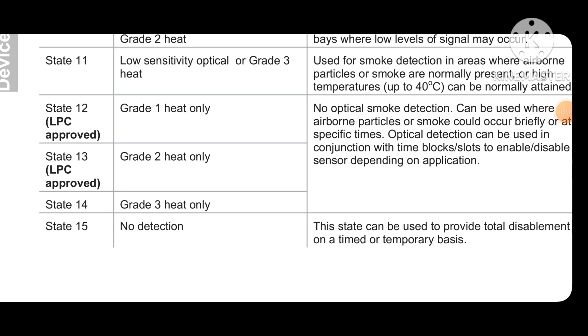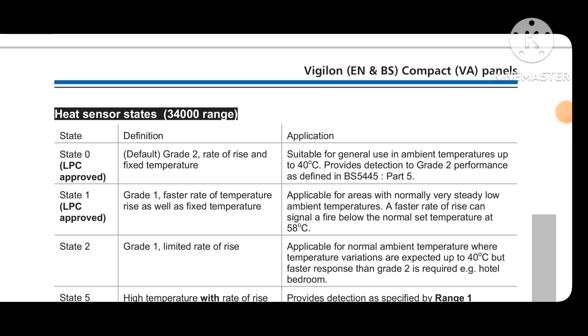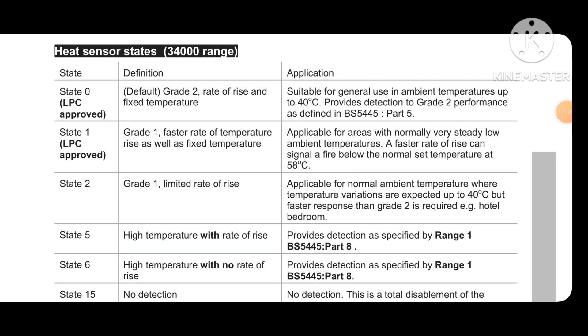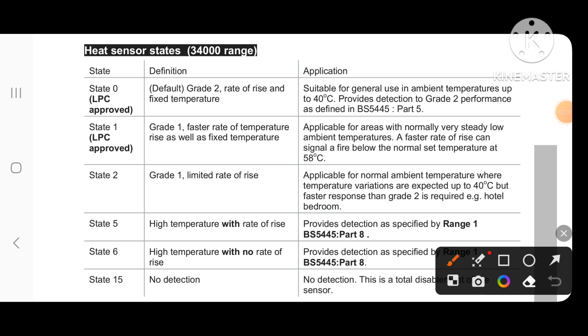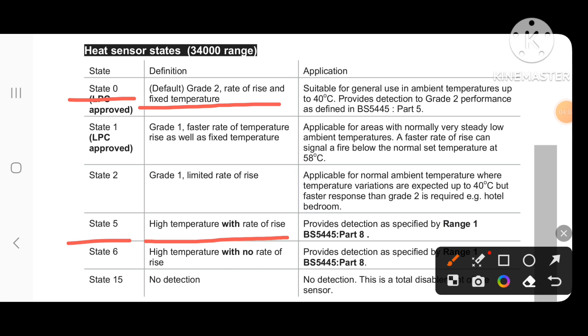State 15 means no detection direction. For heat sensor states, state 0 is the default grade — rate of rise and fixed temperature — suitable for ambient temperature up to 40 degrees, providing detection as defined by BS5445: Part 5. State 1 gives a faster rate of temperature rise as well as fixed temperature. State 2 gives a limited rate of rise. State 5 is high temperature with rate of rise.